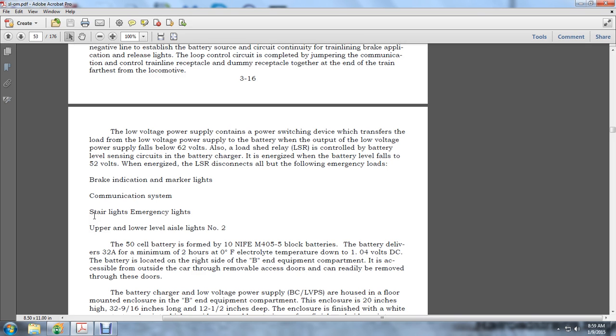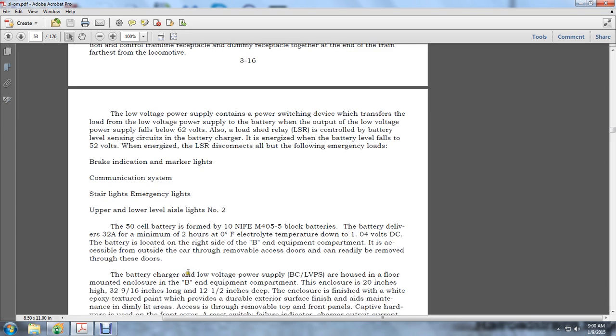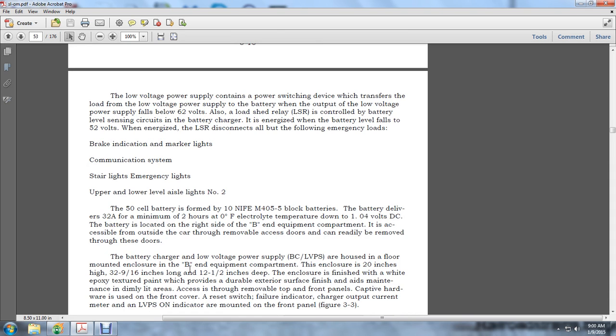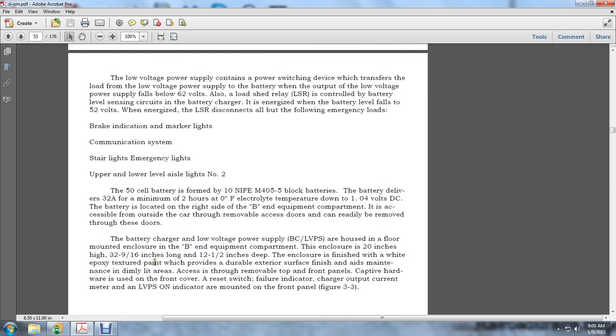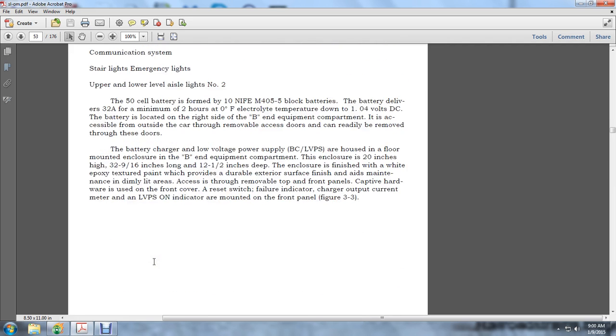The battery charger and low voltage power supply, the BC LVPS, is housed in the floor mounted enclosure of the B end of the equipment compartment. The enclosure is 20 inches high, 32 9/16 inches long, and 12 1/2 inches deep. The enclosure is finished with white epoxy textured paint that provides a durable exterior surface finish and aids maintenance in dimly lighted areas. Access is through the removable top of the front panel, and captive hardware is used on the front of the cover. A reset switch, a failure indicator, the charger output current meter of the LVPS, and the indicator are mounted on the front panel in Figure 3.3.